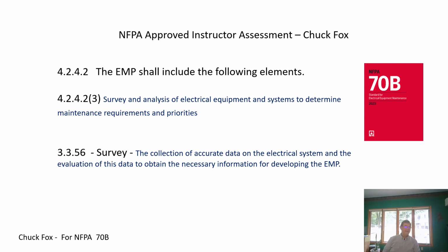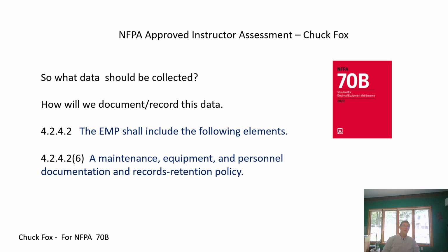The term survey is also defined within Chapter 3 definitions of 70B as the collection of accurate data on the electrical system and the evaluation of this data to obtain the information necessary for developing and implementing the electrical maintenance program. So the question then is, what data should be collected and how will we document and record that data?